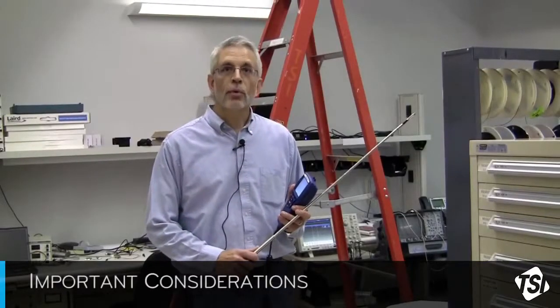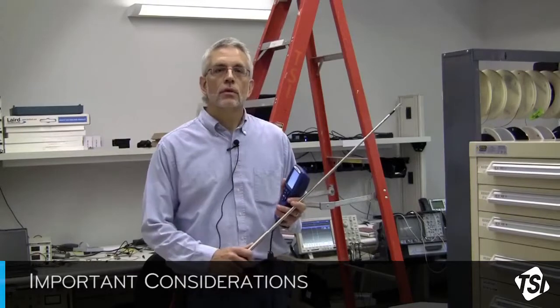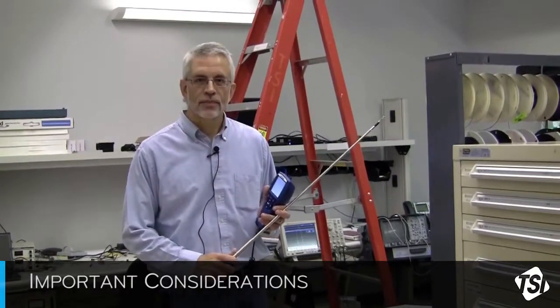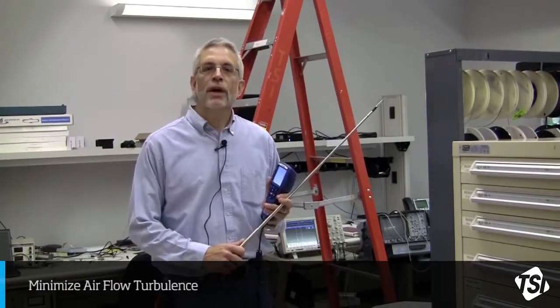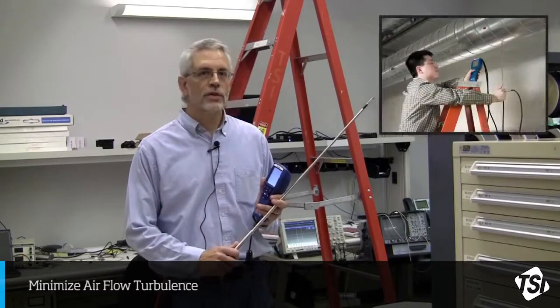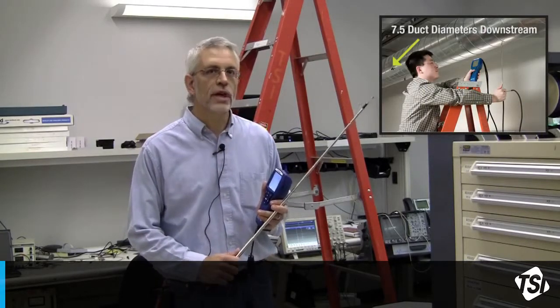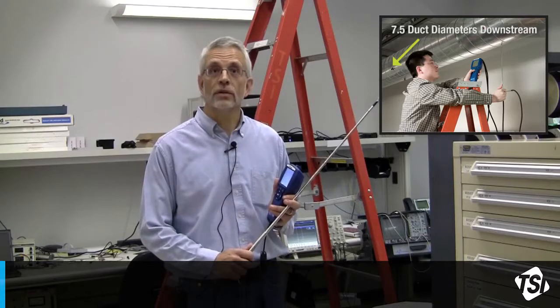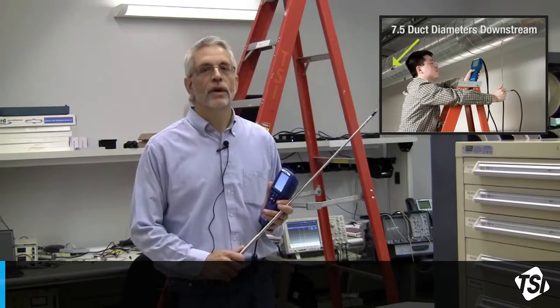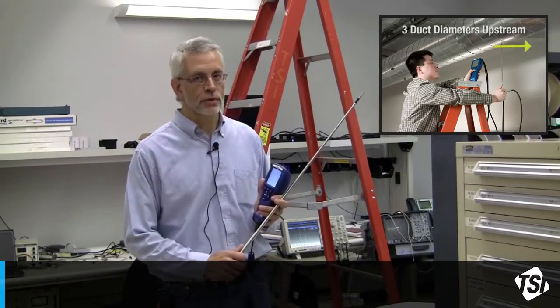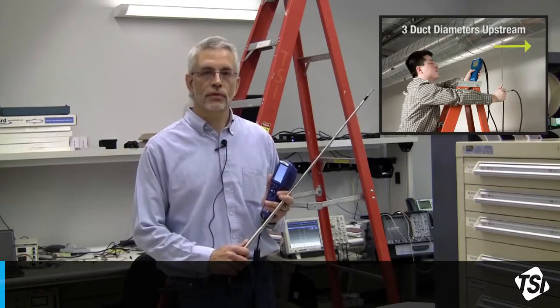There are a couple of important considerations when we do a duct traverse. It's considered best practice to find a location that's 7.5 diameters downstream of any duct or flow obstruction and 3 diameters upstream of any flow disturbance.